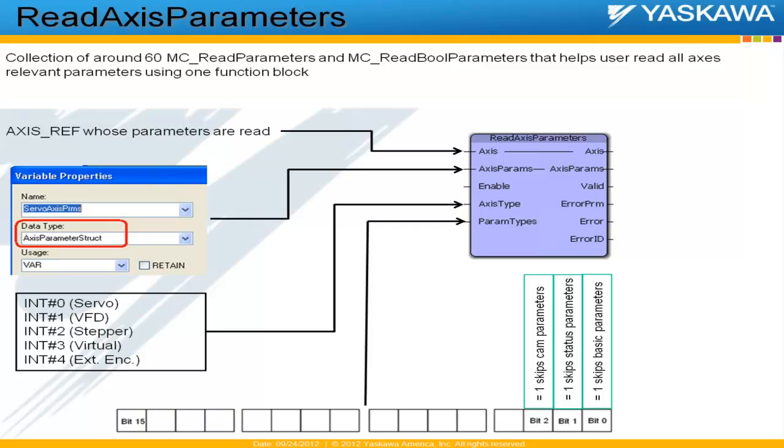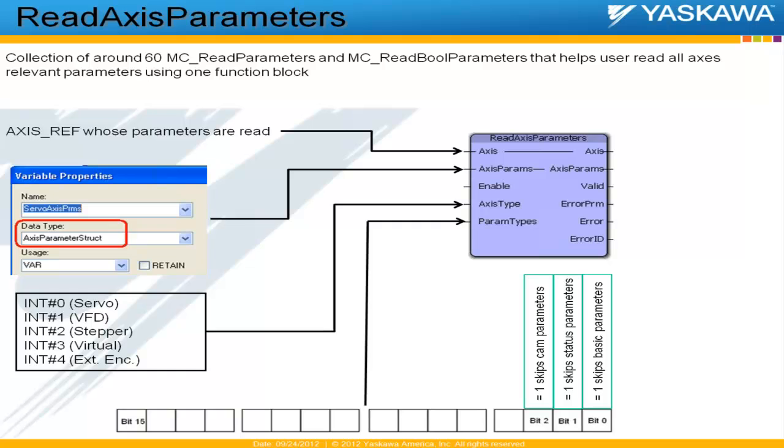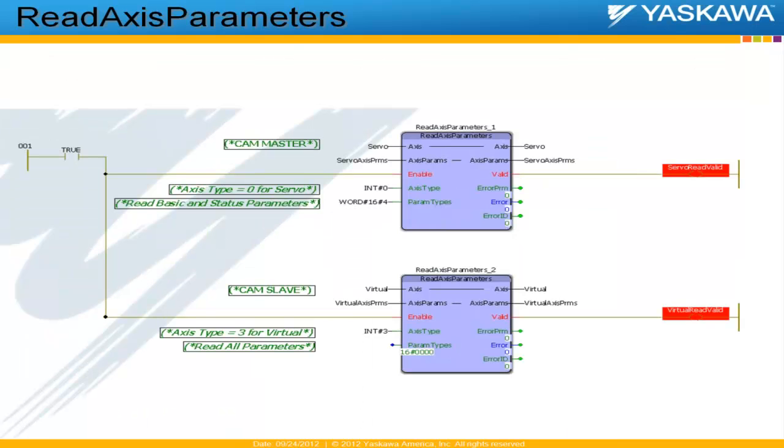For example, if there is a camming application, the master axis in question does not have cam parameters. All the cam parameters are relevant only for slave axes. So, depending on the type of axis and the type of configuration we have for a particular axis, we can choose to read or skip reading a few of the parameters. And again, this param types input is an input that can be used to mask certain read functions.